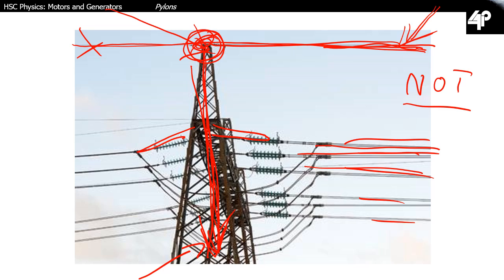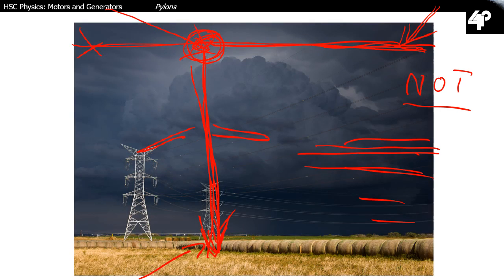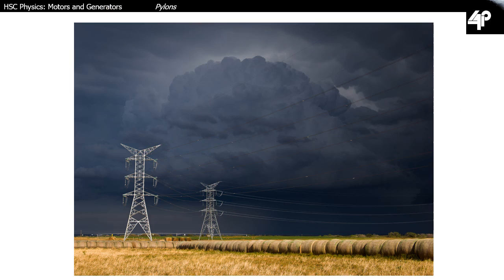So the second option is when the lightning hits the static line. Let's say I hit the static line there. Instead of traveling through the pylon, it travels horizontally along the static line, and eventually reaches a point where it is sufficiently grounded, such as the next pylon along, or any other pylon nearby that is grounded in such a way that the lightning will take a path to ground that way.